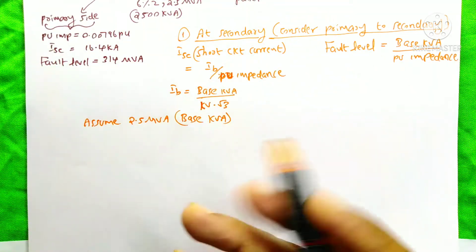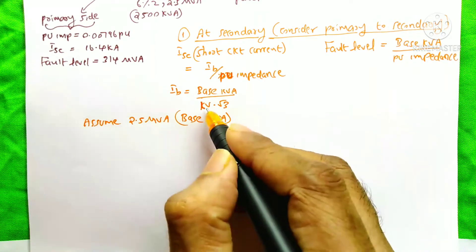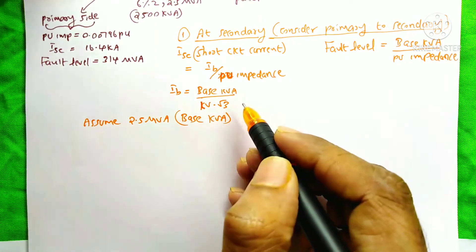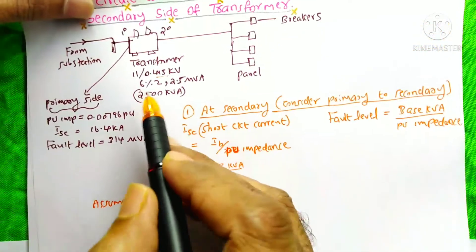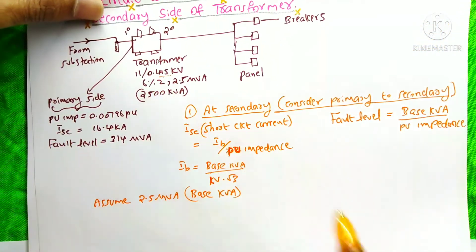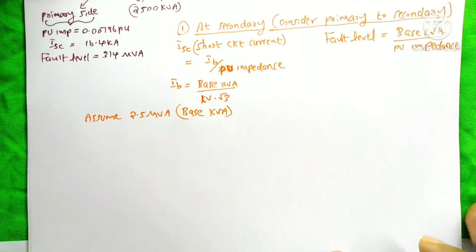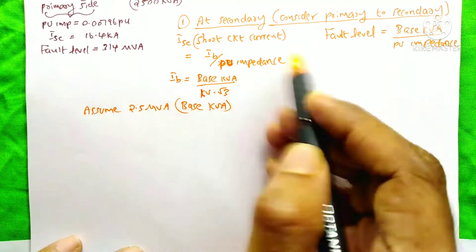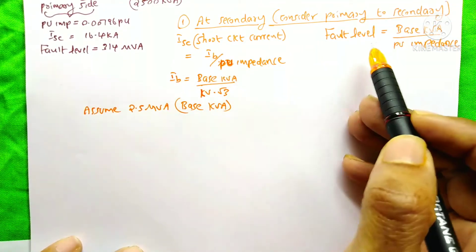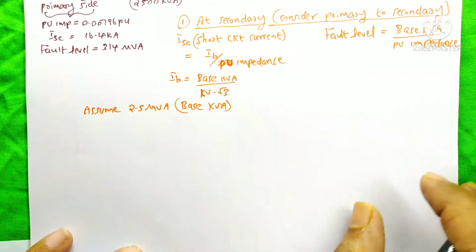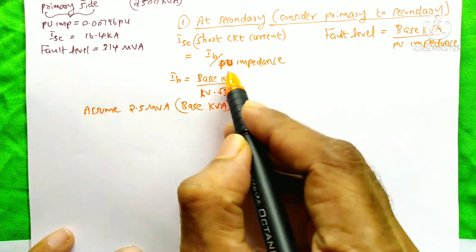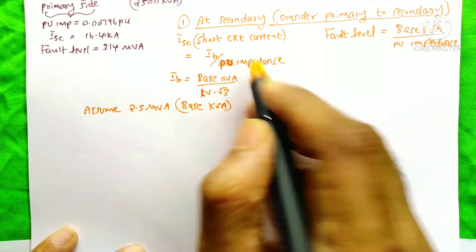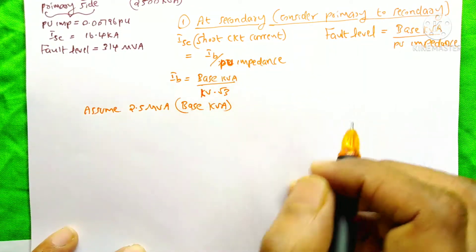The kV at the secondary side is 0.415 kV. To calculate the short circuit current and fault level, one missing factor is the per unit impedance. So we need to find this per unit impedance. If you don't have it, and you only have the short circuit current or fault level, you can find the per unit impedance because ISC equals IB divided by per unit impedance, or the fault level equation is base kVA divided by per unit impedance.